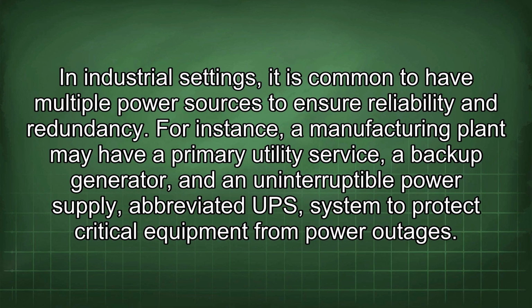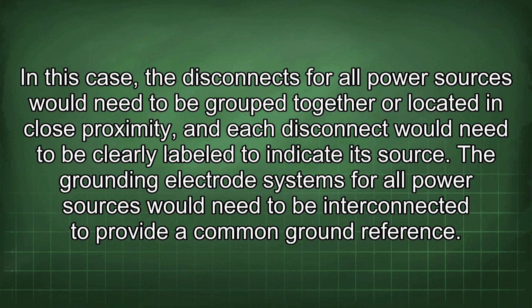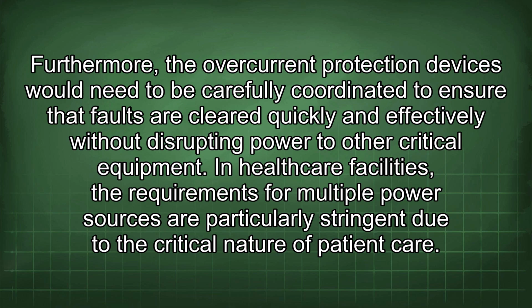In industrial settings, it is common to have multiple power sources to ensure reliability and redundancy. For instance, a manufacturing plant may have a primary utility service, a backup generator, and an uninterruptible power supply, abbreviated UPS, system to protect critical equipment from power outages. In this case, the disconnects for all power sources would need to be grouped together or located in close proximity, and each disconnect would need to be clearly labeled to indicate its source. The grounding electrode systems for all power sources would need to be interconnected to provide a common ground reference. Furthermore, the overcurrent protection devices would need to be carefully coordinated to ensure that faults are cleared quickly and effectively without disrupting power to other critical equipment.